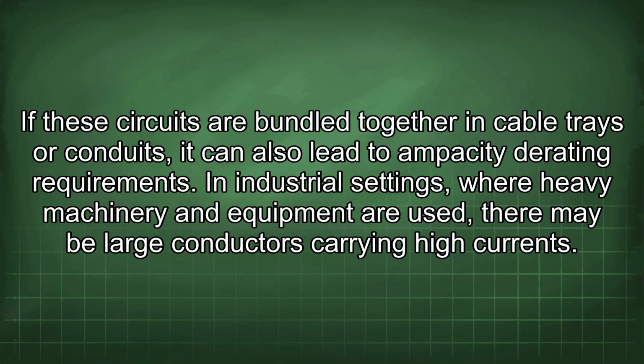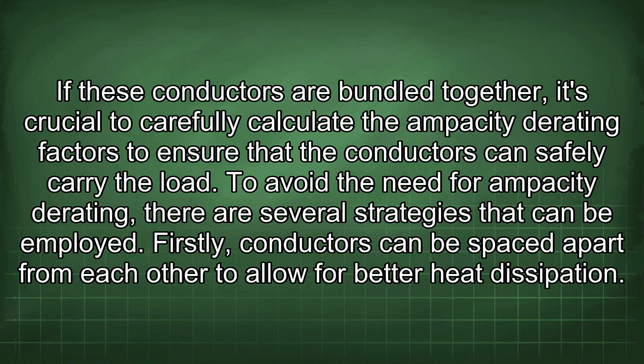In industrial settings, where heavy machinery and equipment are used, there may be large conductors carrying high currents. If these conductors are bundled together, it's crucial to carefully calculate the ampacity derating factors to ensure that the conductors can safely carry the load.